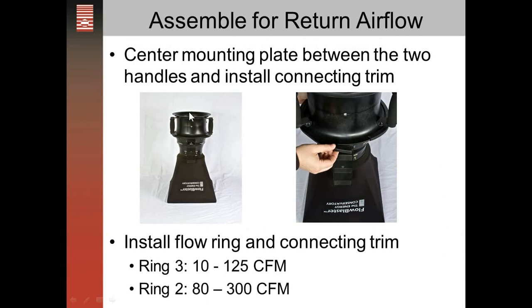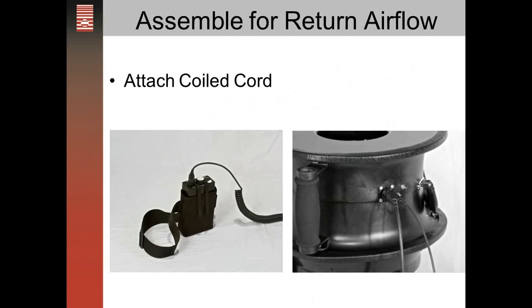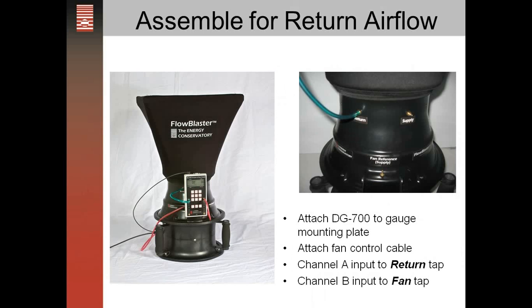When measuring return flow, the flow rings will go on the top, and you use the connecting trim to attach either ring two or ring three. Then attach the coil cord to the battery speed controller and connect the other end to the fan. Attach the gauge to the gauge board, then connect the tubing: on channel A, the input goes from channel A to the return tap on the Flow Blaster housing. The return tap goes to the return flow sensor, which points in the direction of airflow when measuring returns.